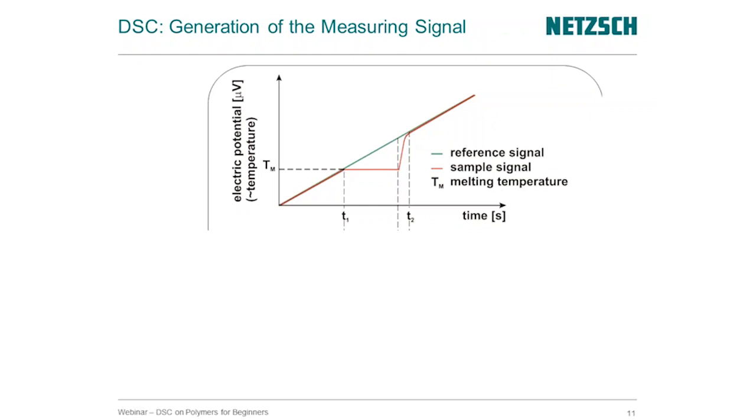Energy goes in until the sample is fully melted, and then once it's fully melted, it begins to catch up with the reference crucible. Okay, so we're looking here on this left-hand axis at a microvolt signal, again, the electrical potential of the thermocouple, and we're looking at that on the x-axis as a function of time.